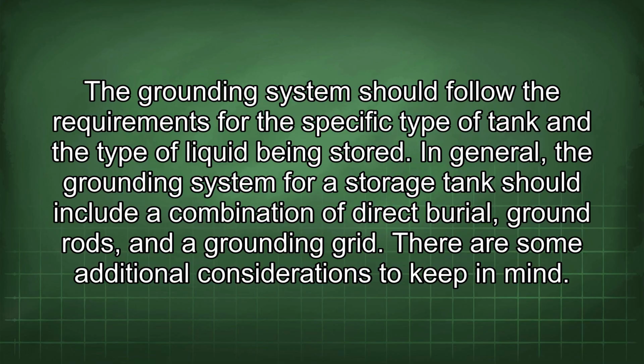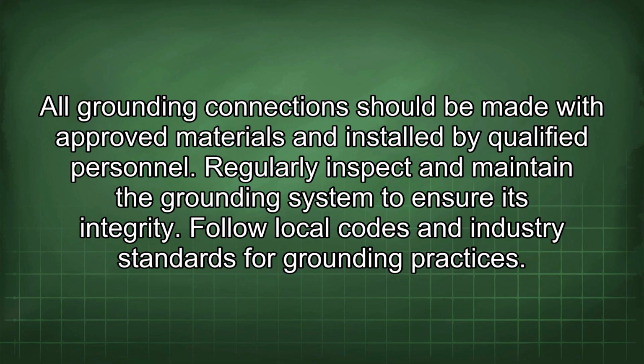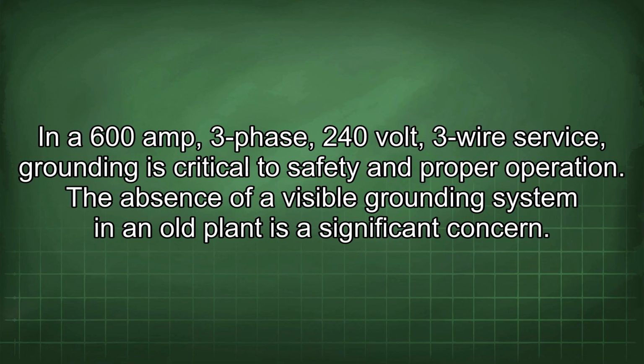There are some additional considerations to keep in mind. All grounding connections should be made with approved materials and installed by qualified personnel. Regularly inspect and maintain the grounding system to ensure its integrity. Follow local codes and industry standards for grounding practices. In a 600 amp, 3-phase, 240 volt, 3-wire service, grounding is critical to safety and proper operation. The absence of a visible grounding system in an old plant is a significant concern.